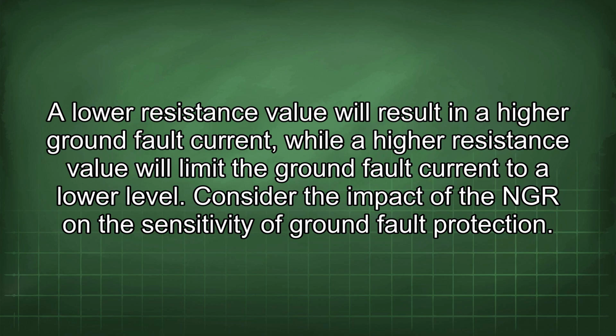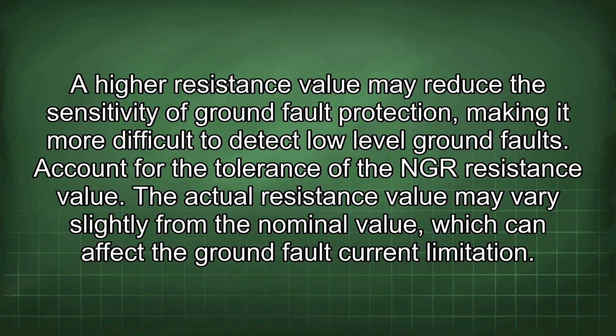A lower resistance value will result in a higher ground fault current, while a higher resistance value will limit the ground fault current to a lower level. Consider the impact of the NGR on the sensitivity of ground fault protection. A higher resistance value may reduce the sensitivity of ground fault protection, making it more difficult to detect low-level ground faults. Account for the tolerance of the NGR resistance value. The actual resistance value may vary slightly from the nominal value, which can affect the ground fault current limitation.